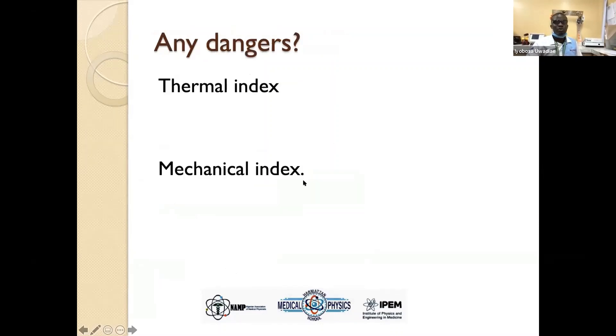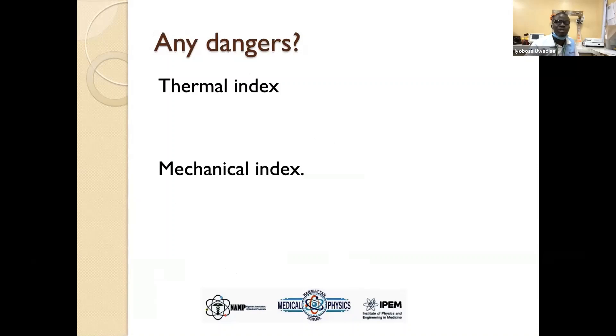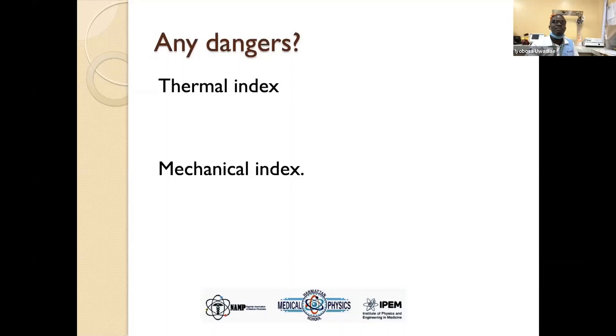Are there dangers with ultrasound? Though ultrasound poses no real danger, we have to be very careful. Medical physicists are called upon to check these indices: the thermal index, which tells us about the heating effect of ultrasound, and the mechanical index, because ultrasound can also be used as a therapeutic agent — for example, in crushing kidney stones. We have to be sure the ultrasound machine is working at an optimal level. We don't use it at excessively high intensities because it poses some subtle dangers.